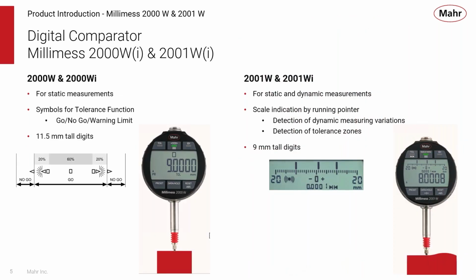So we have two new comparators. We have the 2000 W and the 2000 WI, and then the 2001 W and 2001 WI. The difference between the W and the WI version is that the I stands for integrated wireless. So any model with an I will have Mahr's integrated wireless capability and will be able to communicate wirelessly to a computer. The 2000 model itself is for static measurements, designed for simple static measurements such as heights and diameters. It has a built-in tolerance function with go, no-go, and warning limit features. It also has 11.5 millimeter tall digits for a nice, crisp, easy to read display.